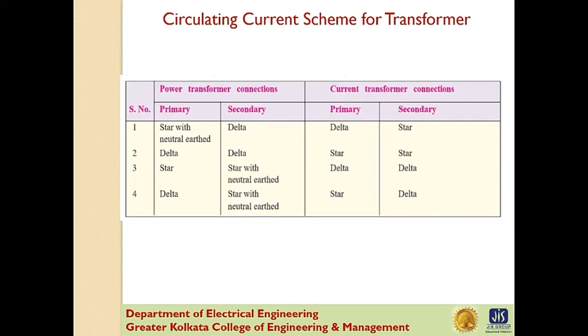This figure shows a Merz-Price circulating current scheme for the protection of a three-phase delta-delta power transformer against phase to ground and phase to phase fault. Note that now the CTs on the two sides of the transformer are star connected. This compensates for the phase difference between the power transformer primary and secondary. The CTs on the two sides are connected by pilot wire and one relay is used for each pair of CTs. During normal operating condition, the secondaries of CTs carry identical current.